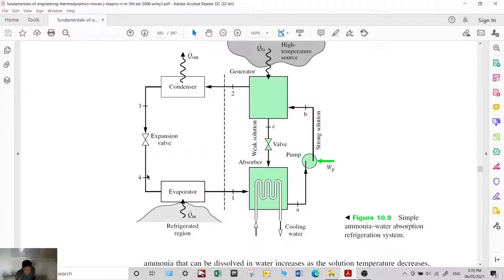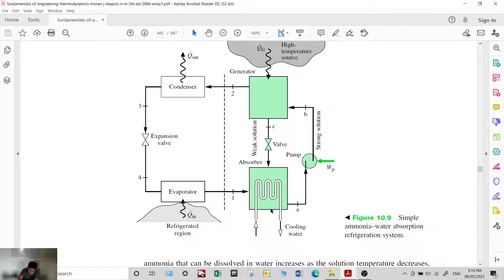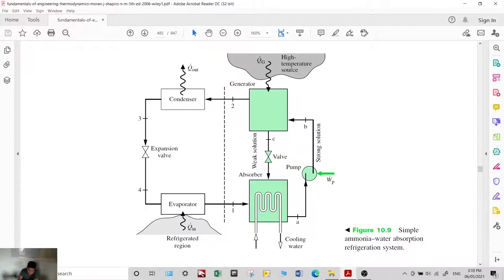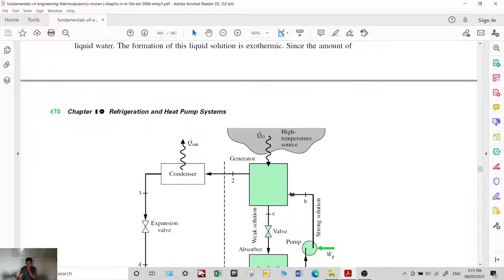The two-phase liquid mixture in the evaporator absorbs heat and exits as vapor. The vapor is then mixed with the absorbent in the absorber, converting it back to liquid form. Once in liquid form, it is pumped to increase pressure and sent to the generator. In the generator, a high-temperature heat source — which can be solar energy, renewable resources, or waste heat — is introduced to vaporize the refrigerant. The vapor proceeds to the condenser while the weak liquid solution returns through a valve back to the absorber.